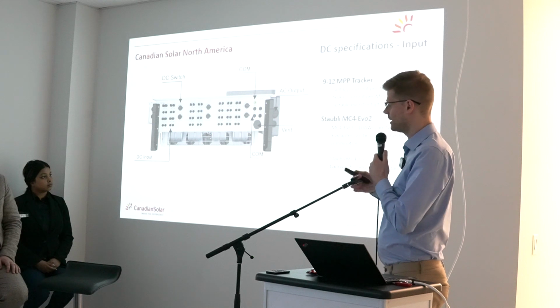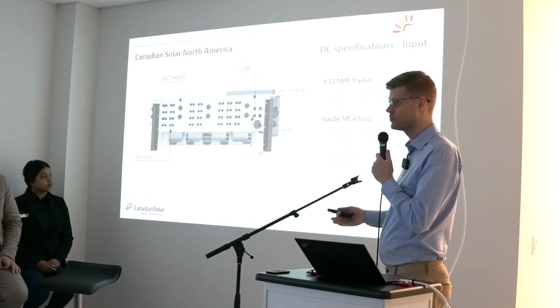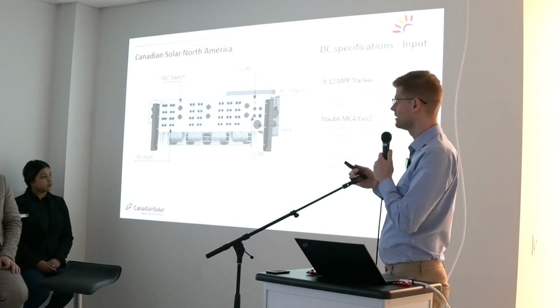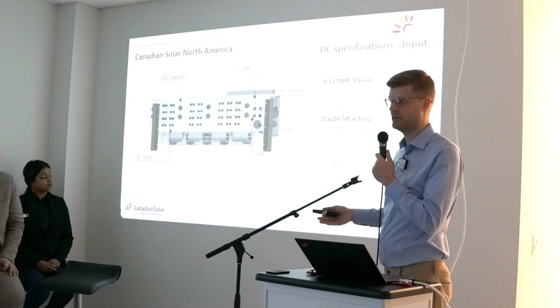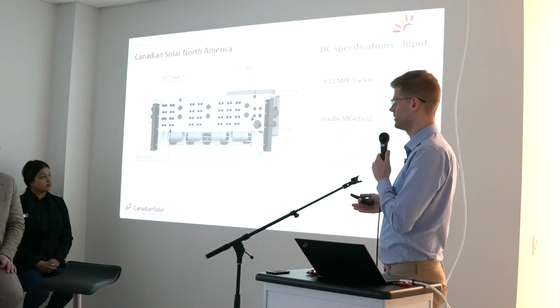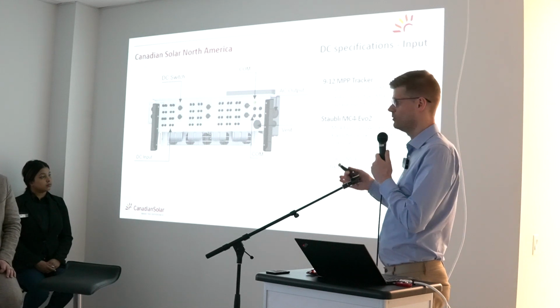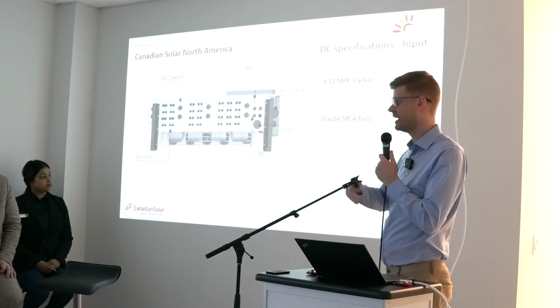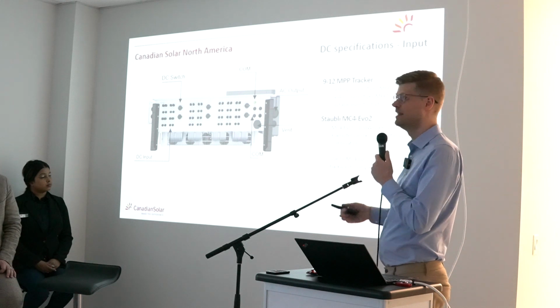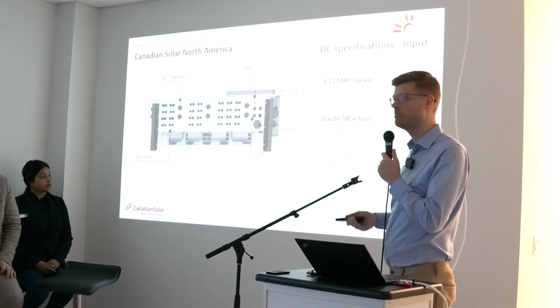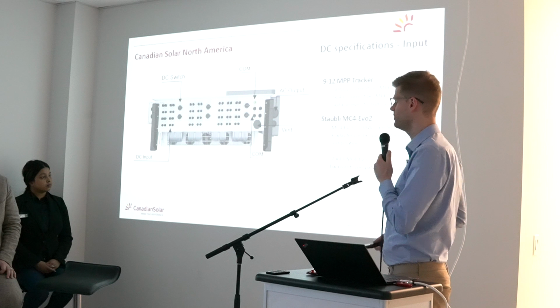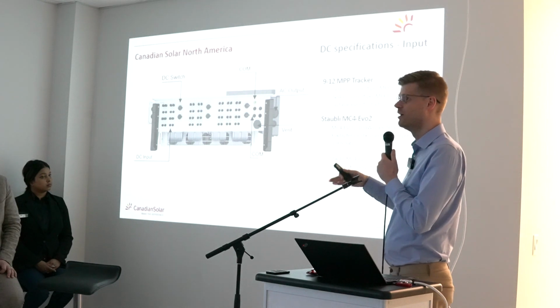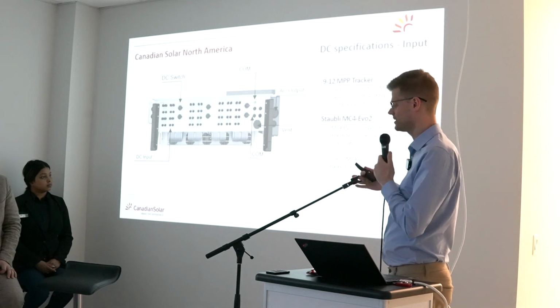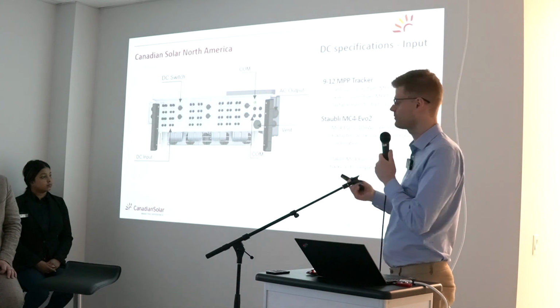Additionally to those separations, you have multiple MPP trackers which allow you to optimize each group of 2 strings, for example, for whatever shading scenarios on a commercial rooftop system, or if you have some long-term degradation of modules over the next 1 or 2 decades, that you have a more granular MPP tracking compared to just a single MPP tracking. That's the concept we see for a lot of manufacturers and a lot of products that are coming to market over the last probably 5 years.